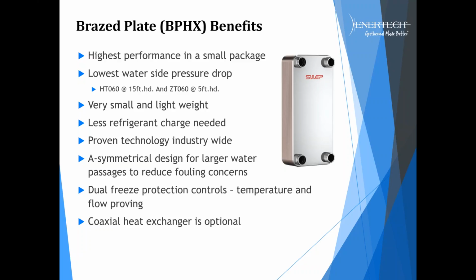We've got a very low water side pressure drop. So, you know, when we talk about EERs with the product, that doesn't even include the pumping power, or the pumping penalty, I should say, as part of that equation. Well, if we look at our old HT product with a coax, we had 15 feet of head for the pumping. With the new ZT060 and the brazed plate, we've cut that down to a third, to 5 feet of head. So much less pressure drop through the water side, which isn't included in the overall EER. And that's a pretty tremendous benefit, really, when you look at an overall project and the system efficiency.